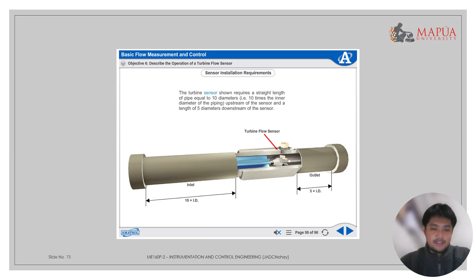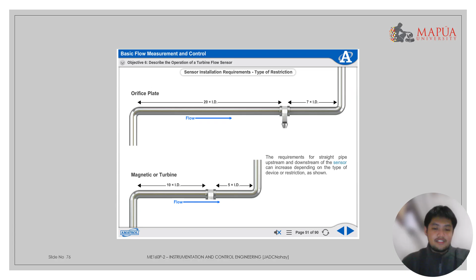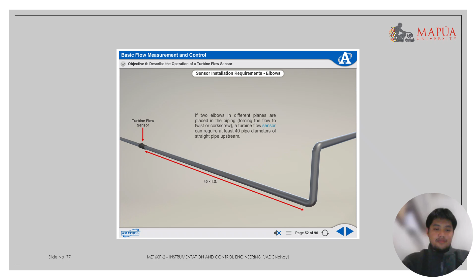Sensor installation requirements by type of restriction. The requirements for straight pipe upstream and downstream of the sensor can increase depending on the type of device or restriction as shown. Now for the sensor installation requirements for elbows. If two elbows in different planes are placed in the piping, forcing the flow to twist or corkscrew, a turbine flow sensor can require at least 40 pipe diameters of straight pipe upstream.